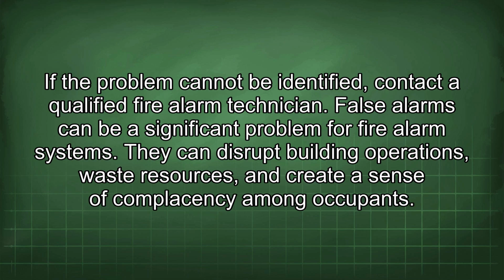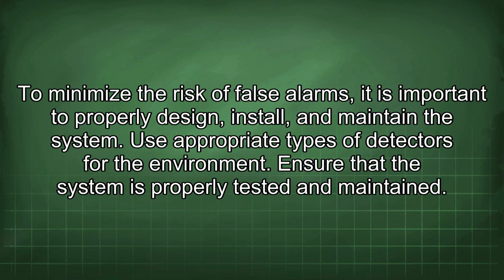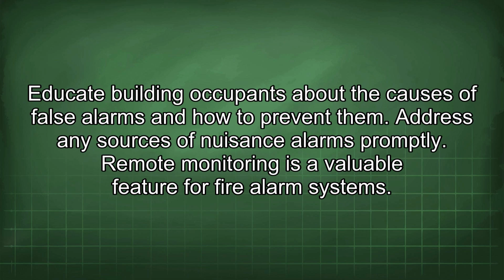False alarms can be a significant problem for fire alarm systems. They can disrupt building operations, waste resources, and create a sense of complacency among occupants. To minimize the risk of false alarms, it is important to properly design, install, and maintain the system. Use appropriate types of detectors for the environment. Ensure that the system is properly tested and maintained. Educate building occupants about the causes of false alarms and how to prevent them. Address any sources of nuisance alarms promptly.